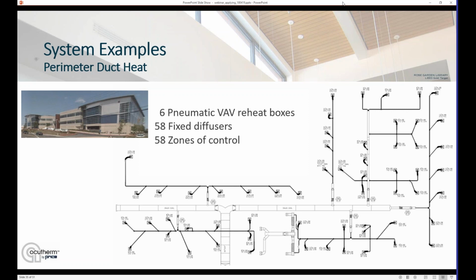Why are the boxes there? Well, number one, the VAV damper is providing our pressure control. This was a partial retrofit of a larger system, so no real control on what the house system was doing, but we're able to create those low pressure zones around the diffusers by using the damper in the VAV box to create our pressure control, and then using the coil in the box to provide the reheat. So while this used to be 26 zones of control, it's now 58 zones of control with the Therma-Fuser diffusers providing those zones throughout the building.